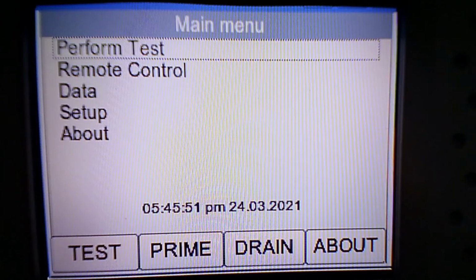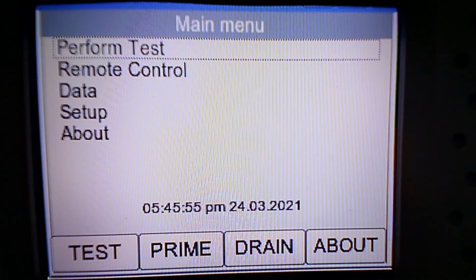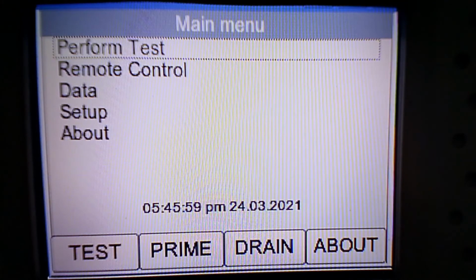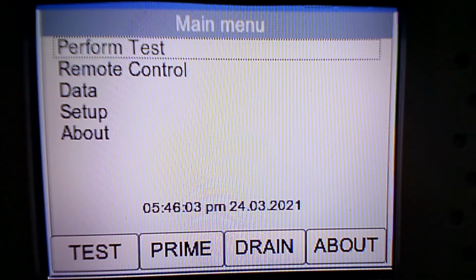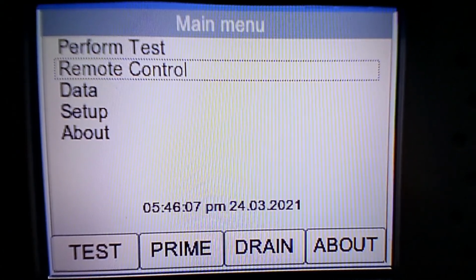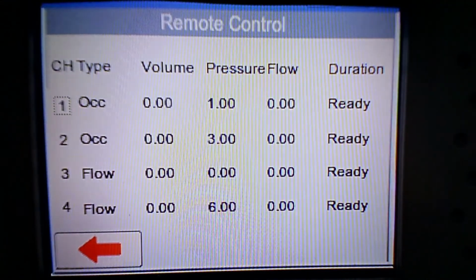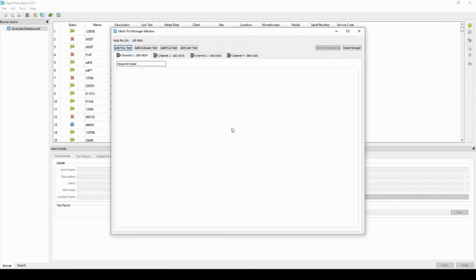Okay, so it's really simple to set up the Multi-Flo for remote control mode. We connect the USB from the PC to the side of the Multi-Flo USB-C port, and then we select the remote control mode here, and now that's ready to be controlled by the PC. Okay, so from tools we select the download icon, make sure that the Multi-Flo is selected, and then we select the remote mode to connect to the COM port. Add a flow test first, show how to do that. We've got duration type, so it can either be volume based or time based, but for this presentation we'll just do time based like we did before, so set a similar duration.